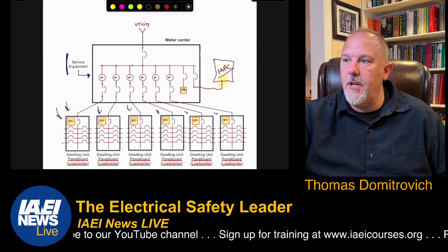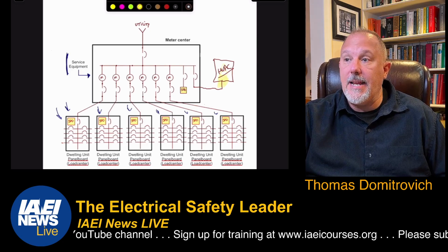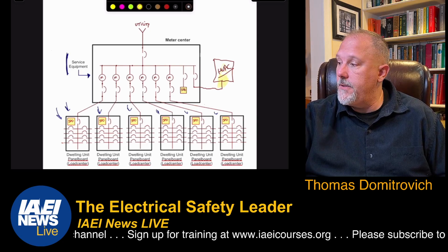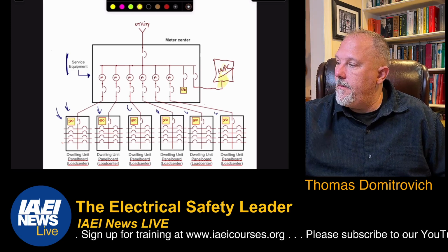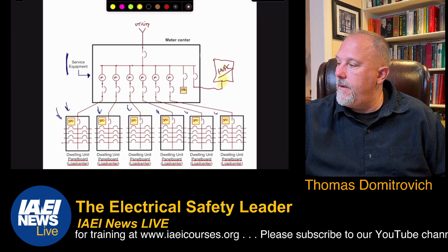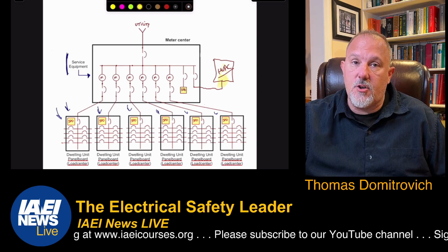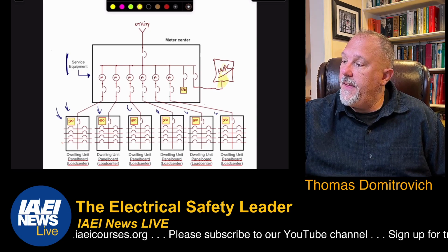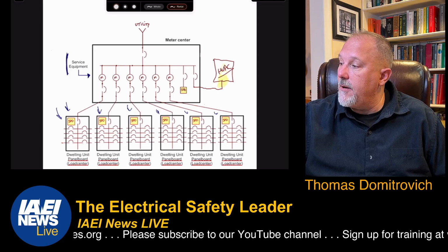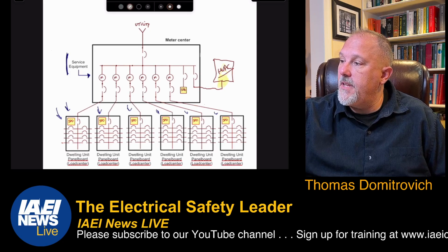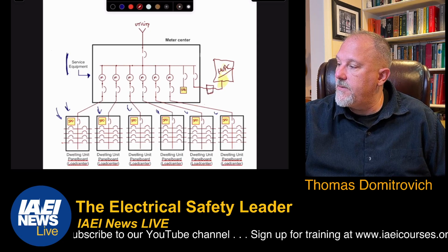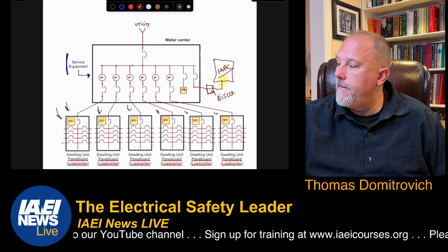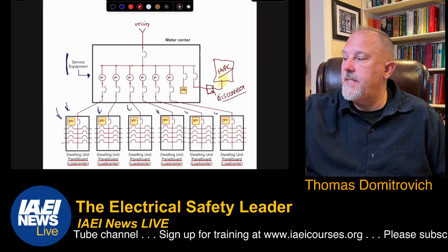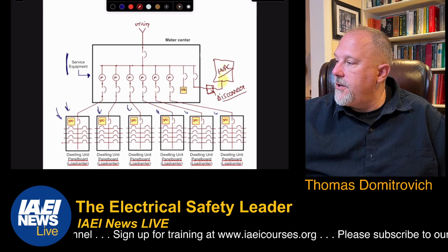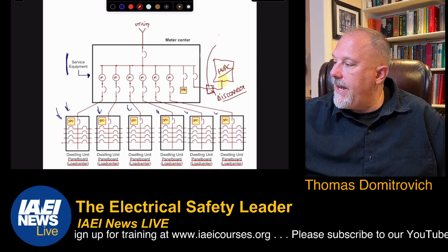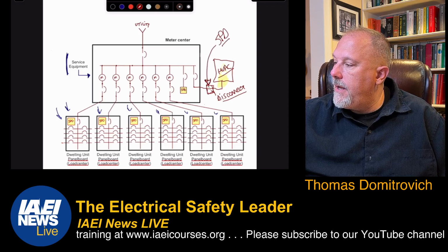SPD shall not be required to be located at the service equipment if located at each next level distribution equipment downstream toward the load. So if you consider the HVAC equipment a load, then you wouldn't need to put a surge protective device there.